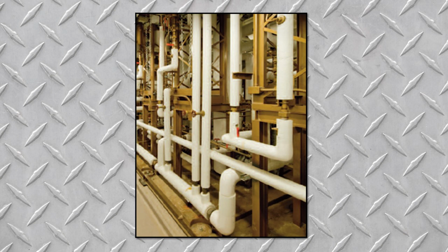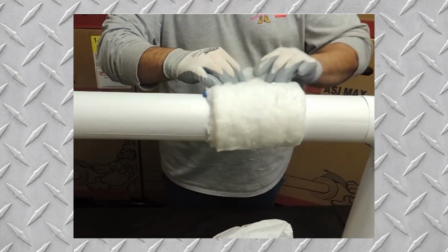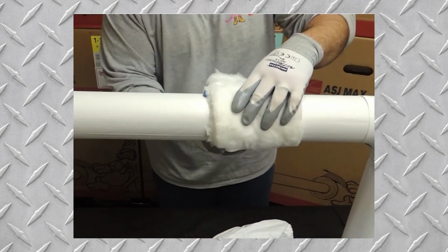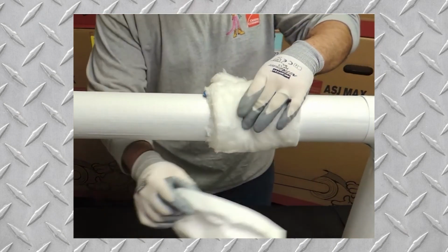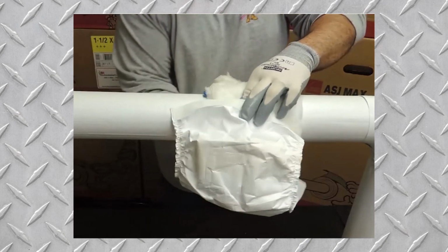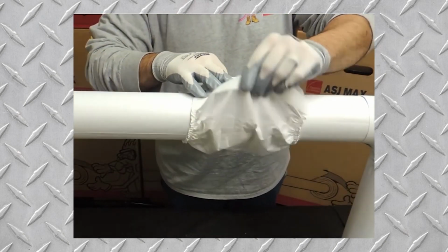As you can see in this picture here, we have white insulation with uninsulated valves connecting different parts. Although it is not commonplace yet, a removable insulating Velcro secured wrap can be added to valves and elbows and things of this nature. And so we can often look at a very small piece of uninsulated steam pipe and make a good recommendation about it.